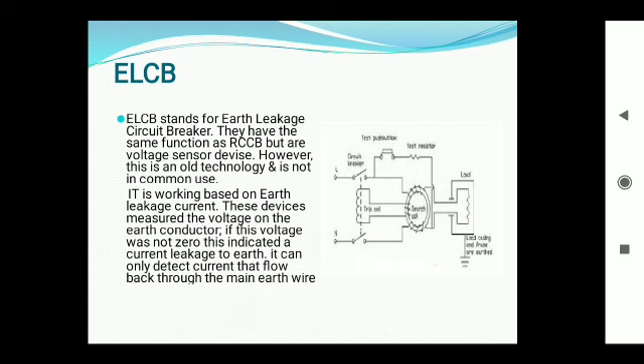It works based on earth leakage current. This device measures the voltage on the earth conductor. If this voltage is not zero, this indicates current leakage to earth. It can only detect the current that flows back through the main earth wire.